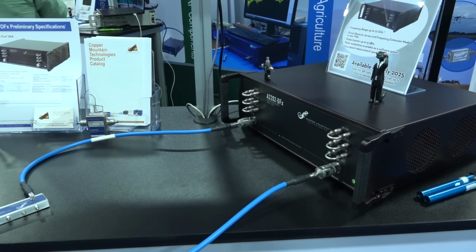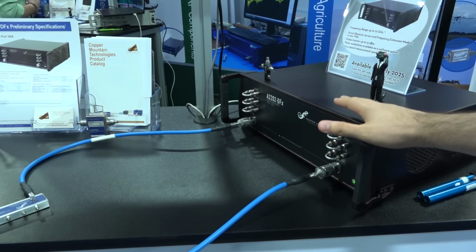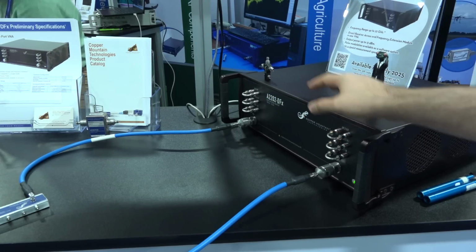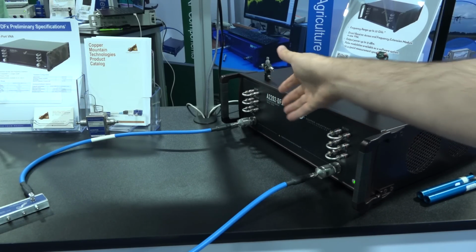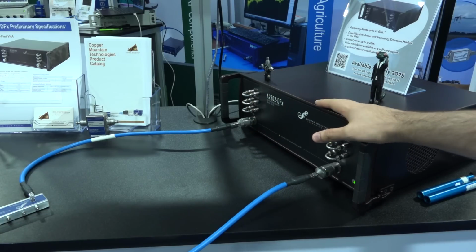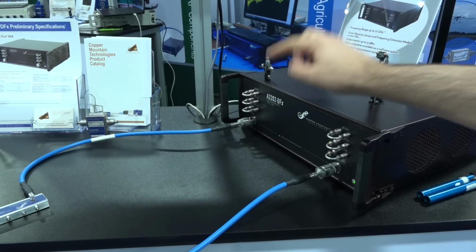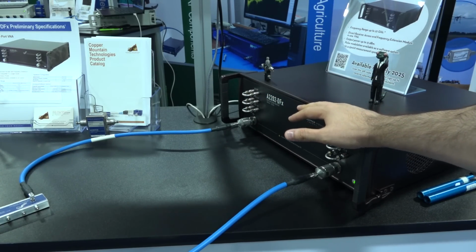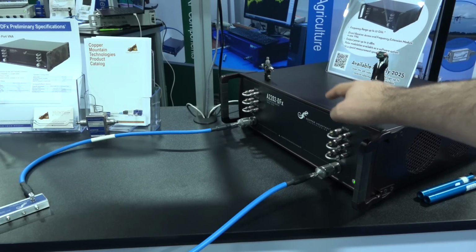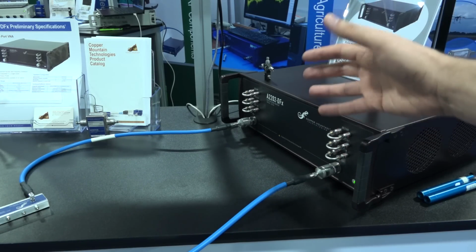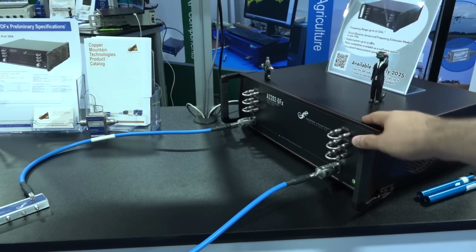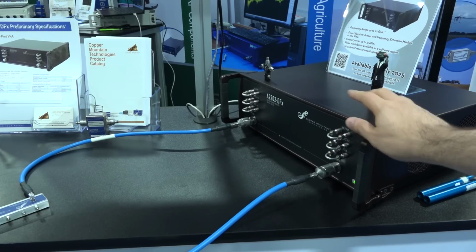And here's a new redesigned network analyzer platform that is going to be available in about a year or so. And this platform has access to all the receivers separately up to 22 gigahertz, which means that you can, of course, put signals into the receivers and allows you to do all the things that extensions allow you to do. But on top of that, at the back, you have the ability to connect to millimeter wave extenders. Now, because of the close collaboration between Copper Mountain and Eravant, a platform like this, combined with their frequency extenders, now all of a sudden becomes a super fast and flexible network analyzer platform all the way to hundreds of gigahertz as this becomes available next year. So looking forward to taking a look at it.